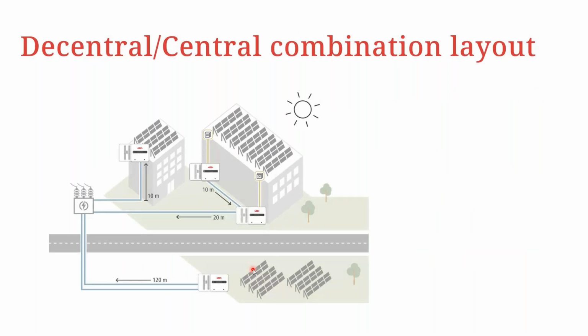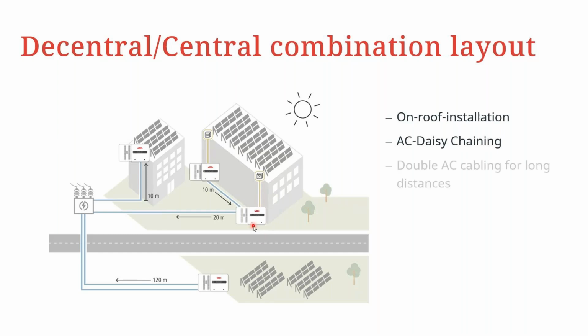It's also possible to have a combo, a both decentralized and centralized combinational layout, as you can see in this case. We have an on-roof installation implemented using DC combiner boxes going to their respective inverters, and then on the AC side they're daisy chained and connected to the inverter. We also have a scenario where another installation site is far from the transformer, and in order to reduce cable cost, you can use half the dimension and go with double cable laying along longer distances to reduce voltage losses along the cables.